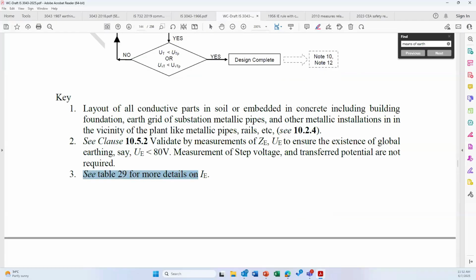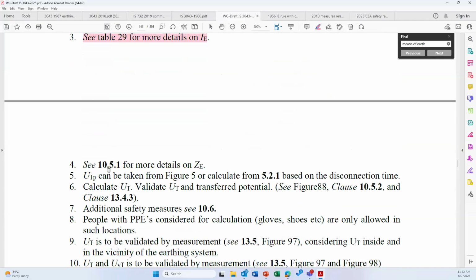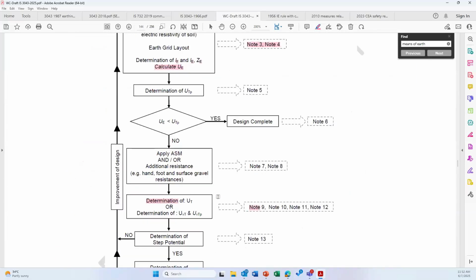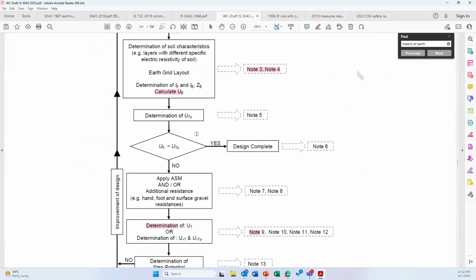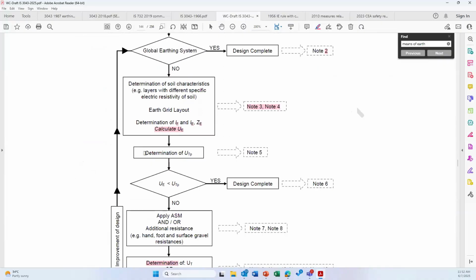Note 3, see table 29 for more details on IE. The current which is flowing through the earth electrode can be calculated based on this. And note 4, 10.5.1 for more details on ZE. So you can find out more information about these two. Then the next step is determination of UTP. UTP is nothing but the prospective touch voltage.